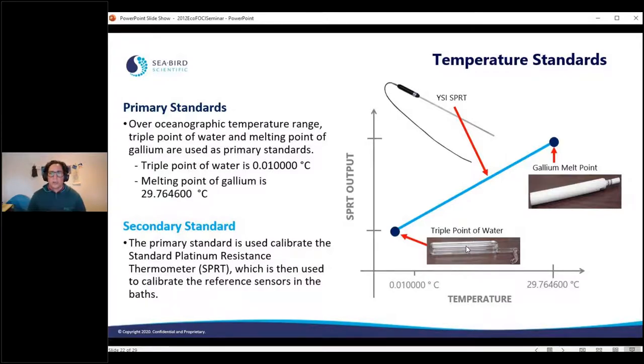This is called a transfer standard. So we take two physical standards, the triple point of water and the gallium melt point, use them to calibrate a secondary standard called a standard platinum resistance thermometer, or SPRT. Then we use that to calibrate another bunch of reference sensors that are used in the bath to calibrate the sensors you use in the ocean.